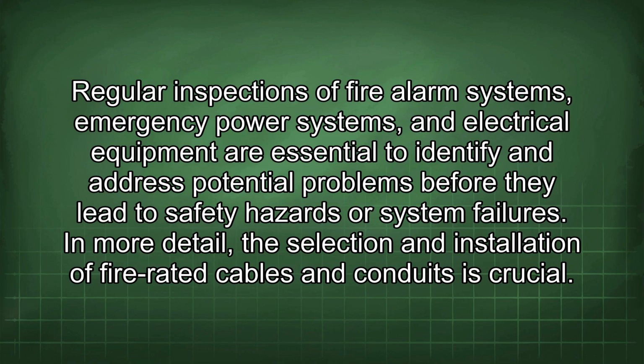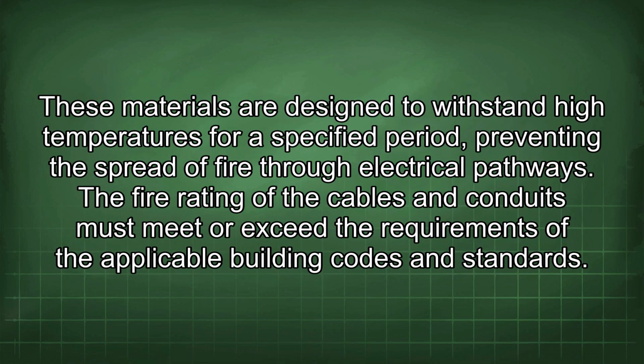In more detail, the selection and installation of fire-rated cables and conduits is crucial. These materials are designed to withstand high temperatures for a specified period, preventing the spread of fire through electrical pathways. The fire rating of the cables and conduits must meet or exceed the requirements of the applicable building codes and standards.